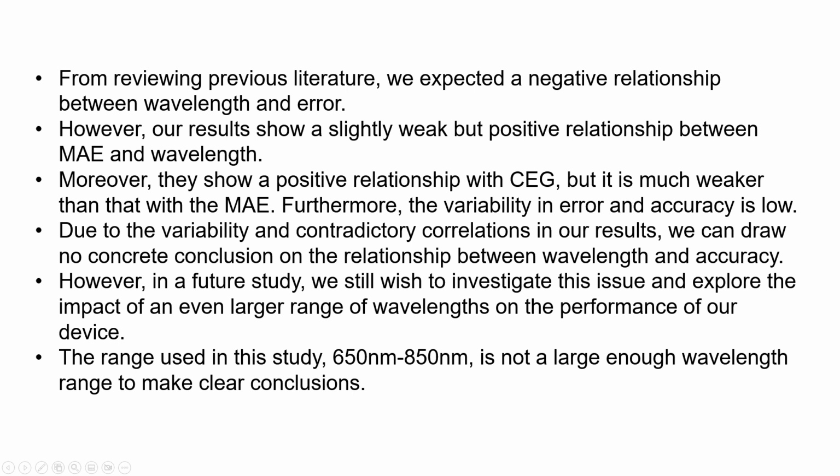between the other, wavelength and CEG, we can't make a clear conclusion on whether wavelength truly improves the performance of the model. However, it should be noted that our study did use a short range for wavelengths, only 650 to 850 nanometers. This is not a large enough wavelength range to make clear conclusions, as many blood glucose monitoring devices and others in the field use much larger wavelength ranges, such as 650 to 1100 nanometers.